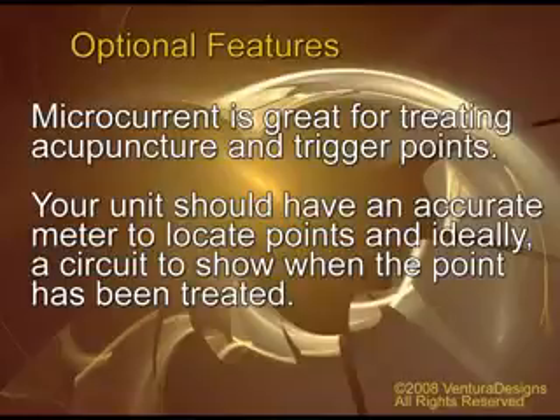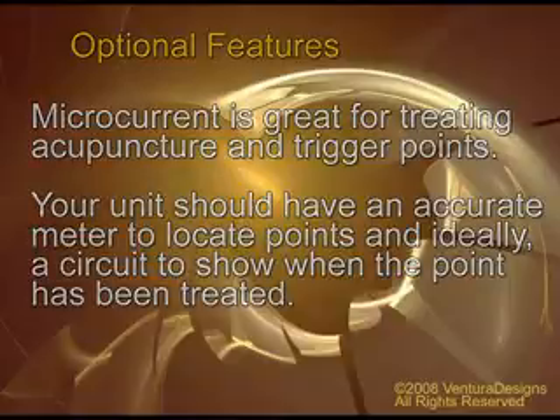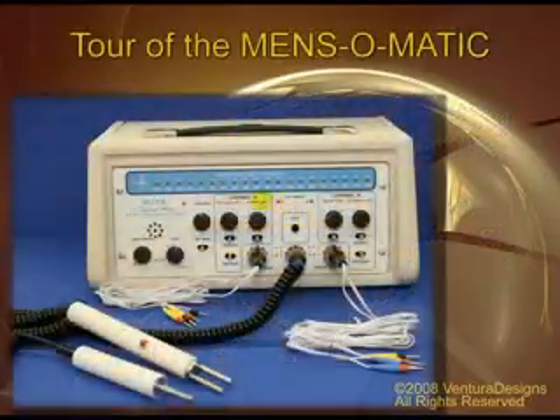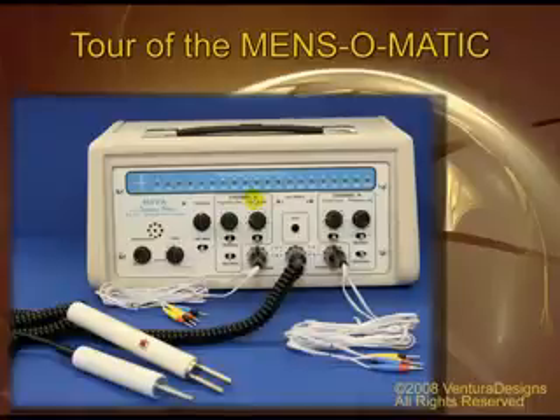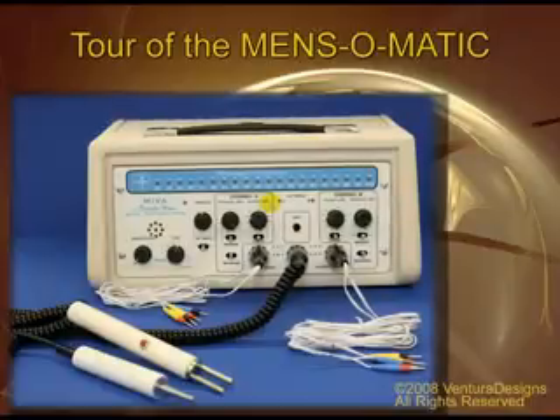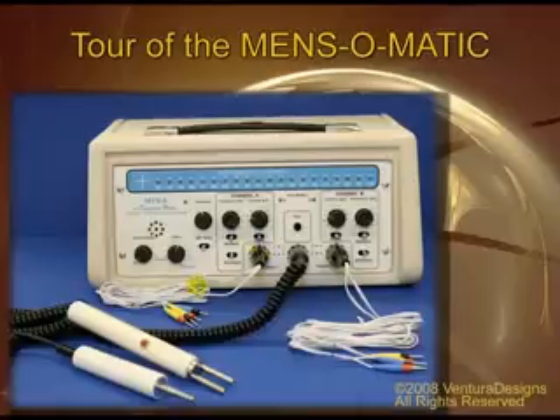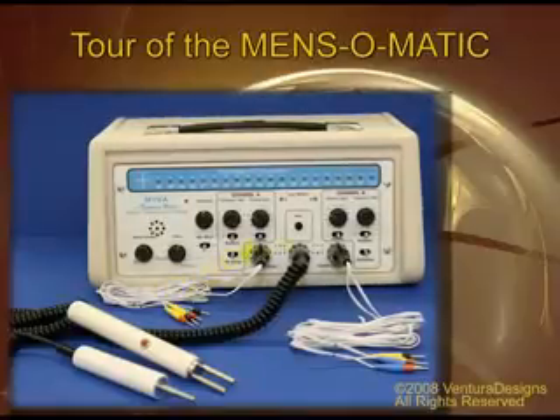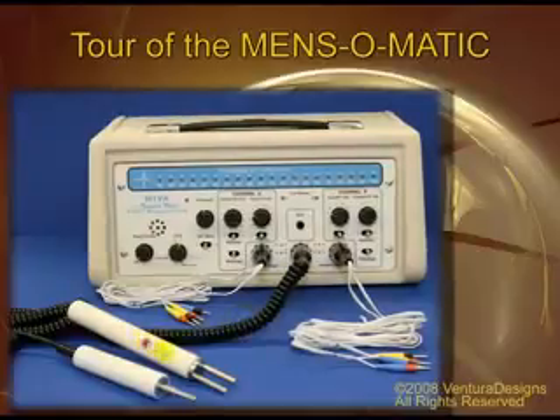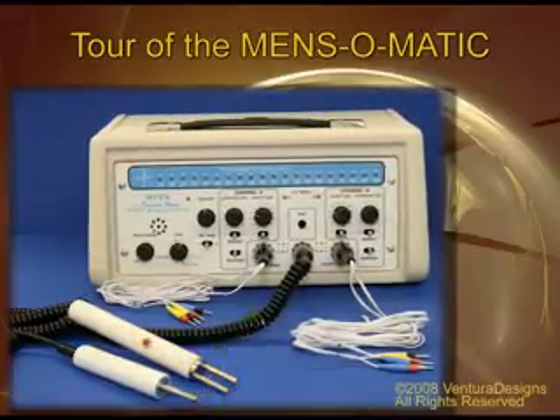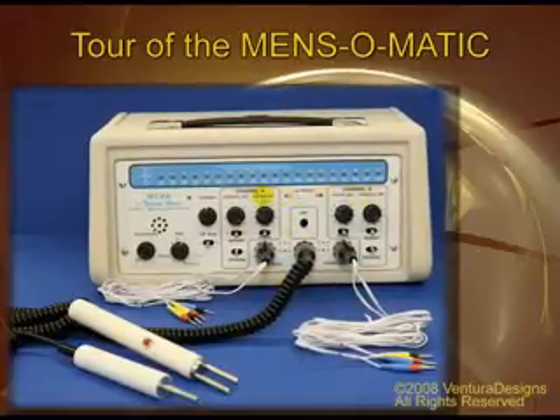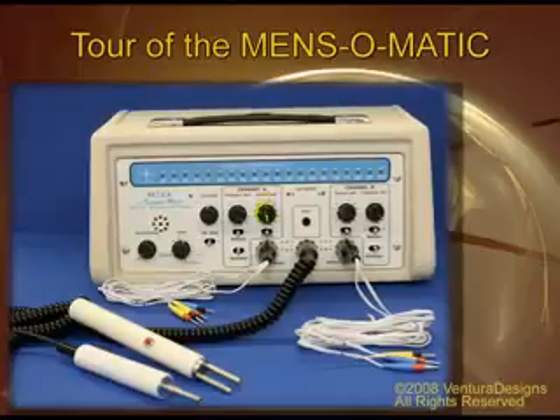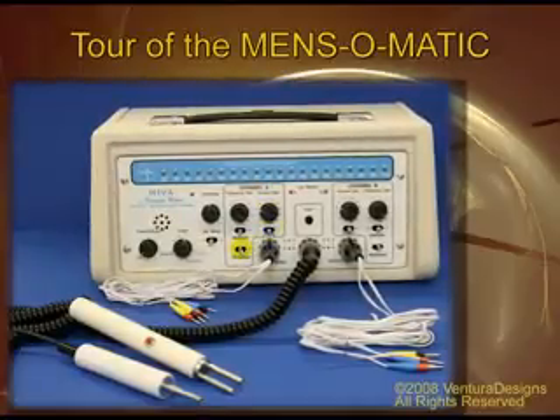Microcurrent is great for treating acupuncture and trigger points. Your unit should have an accurate meter to locate points and ideally a circuit to show when the point has been treated. A tour of the MENS-O-MATIC shows us first that we have 2 channels of stimulation, channel A and channel B. These 2 channels are completely isolated and are independently controlled. Now the current can be delivered either through electrodes and pads or through a probe with the patented Q-tip applicators. Each channel has its own control over frequency and current, and also the polarity and the wave slope.